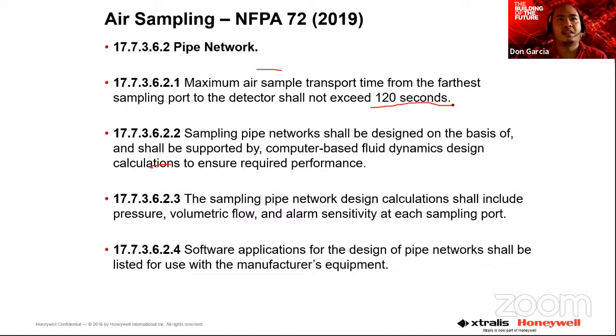Okay? So how do we know that you pass at the design stage? Every manufacturer of aspirating detectors, including VESDA, has a computer-based fluid dynamic design calculation. We have software that we use for VESDA, and for Xtralis, you are using ASPIRE design software. This software is used to calculate the pressure, volumetric flow, alarm sensitivity, and also the transport time that we mentioned, before we do the installation or before we submit the design for approval. So here we will know that we passed, or that we met the criteria of the air sampling requirements of NFPA.